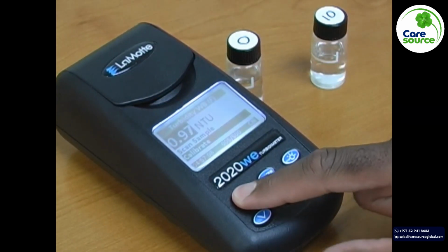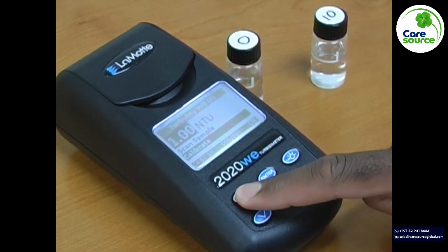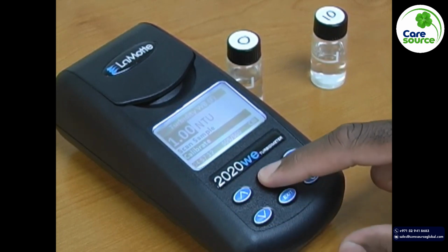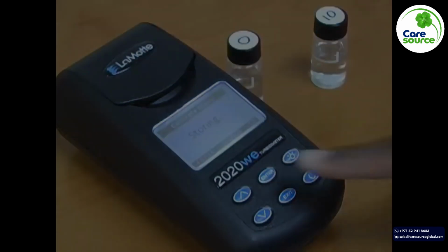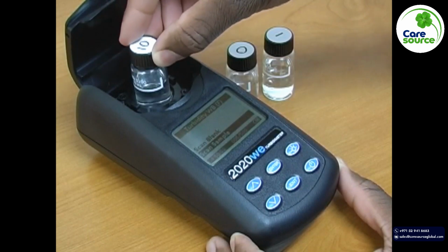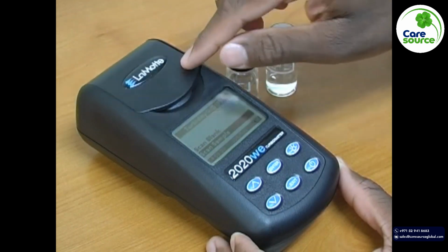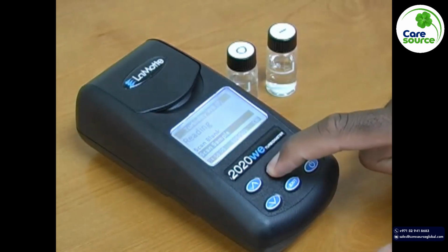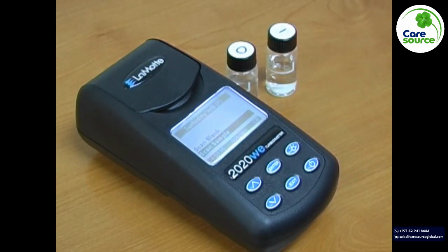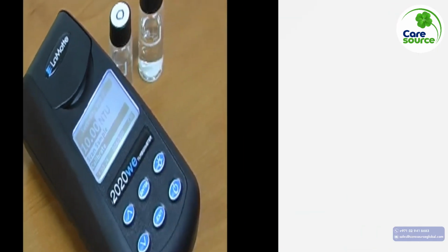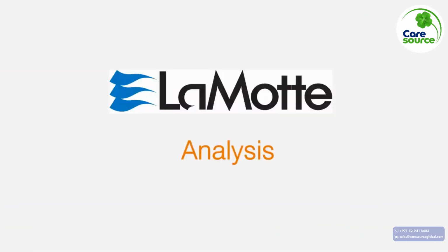Use the up and down arrow buttons to adjust the calibration to 1 and press Enter to store. To calibrate the meter across a larger range, follow the same procedure for the 0 and then use the 10 NTU standard to calibrate. Your meter is now calibrated and ready to use.